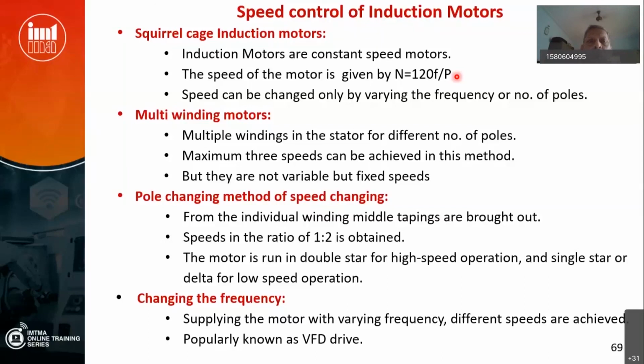That is one method. Next, the same winding can have a tapping from the middle, called delta double star. When you connect the 3 windings of the 3-phase motor in delta, you get one speed. The second time you make it double star. I am unable to show the figure here. In a double star connected motor, you will have a center tap from each phase, so there will be 9 terminals in the motor: start and end of 3, and again 3, 6 plus 3. Connect them in double star mode, and you will get another speed.